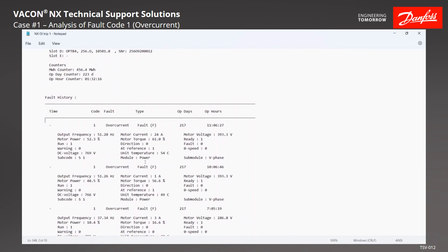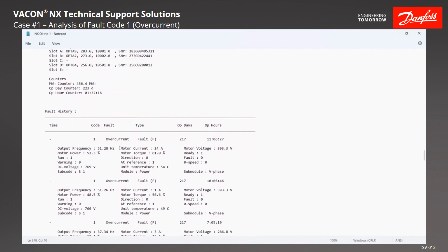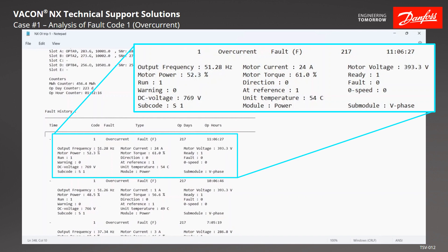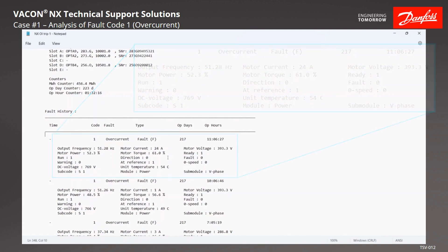Let's look at what data here is correct and what isn't. For an overcurrent trip, we go to motor current first. We see 24 amps captured. Now some of this data we need to take with a grain of salt. This data is sampled at a certain rate — we don't have enough microprocessor speed to sample continuously. It's sampled roughly every 10 milliseconds, so this is basically what's monitored on the HMI screen. When it samples the data it puts that in the buffer, and when it gets a fault, everything in the buffer goes into the fault history. So there's a time gap where the data might be a little old.